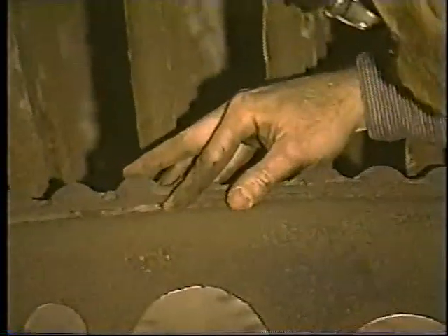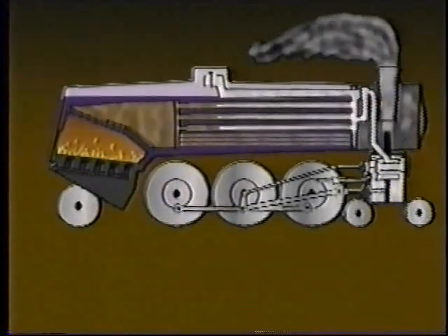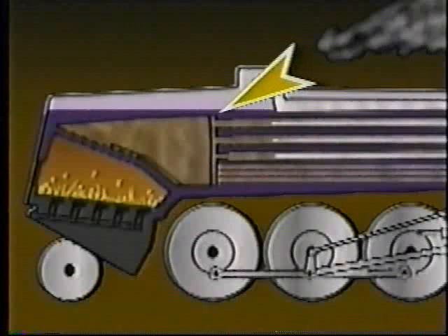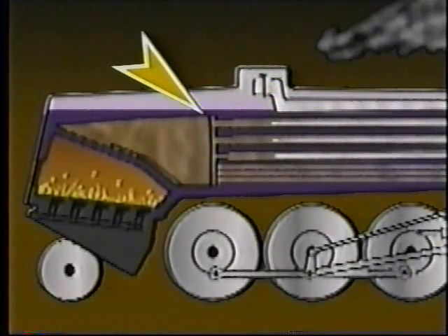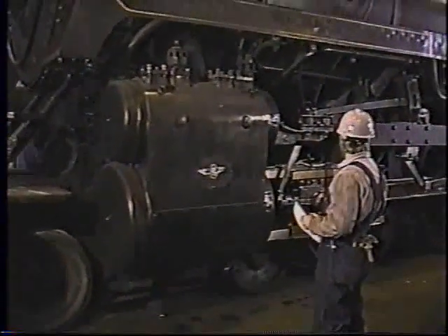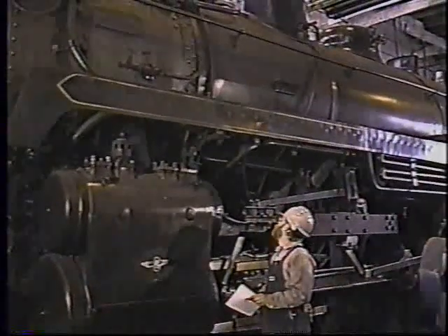Hammer test the dry pipe and listen for sounds of irregular thickness or exceptionally thin spots. Carefully examine the rear flue sheet knuckle at the crown sheet for cracks. This knuckle is susceptible to stress corrosion, cracking and grooving — a result of the curves its position requires and the extreme heat it is subjected to. Slight grooving in the knuckle does not necessarily mean the locomotive must be taken out of service. Some grooving is acceptable and will not affect the performance or safety of the knuckle. Familiarity with each locomotive is the best way to make judgments on situations like stress corrosion and cracking of the knuckle.